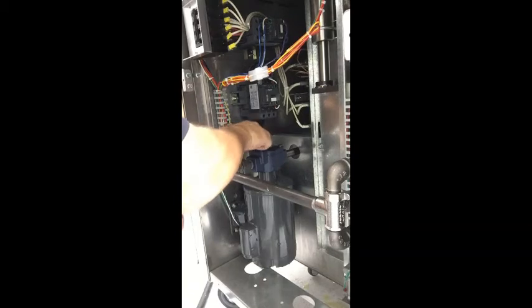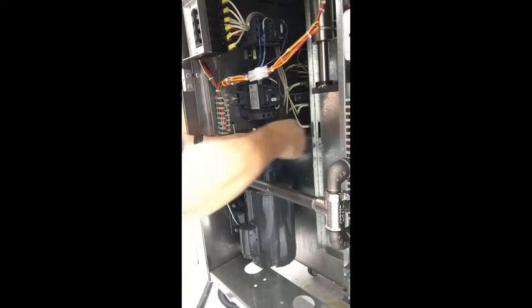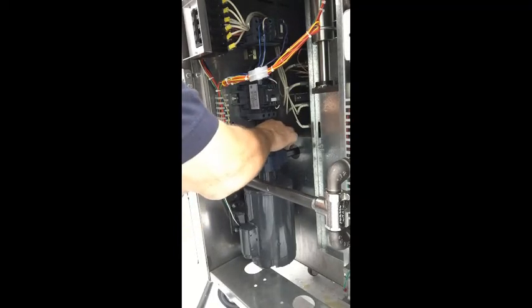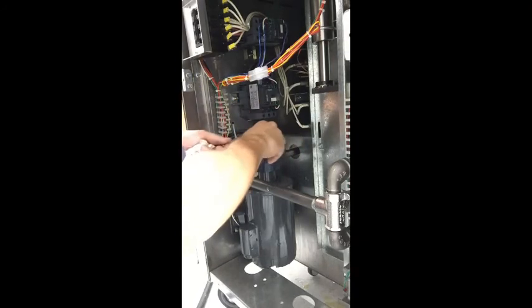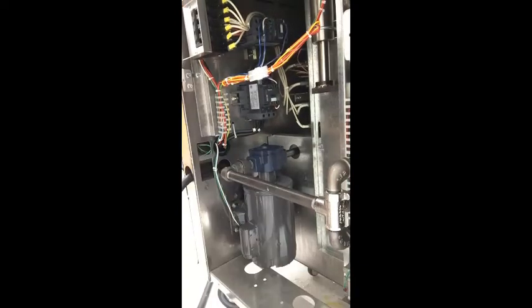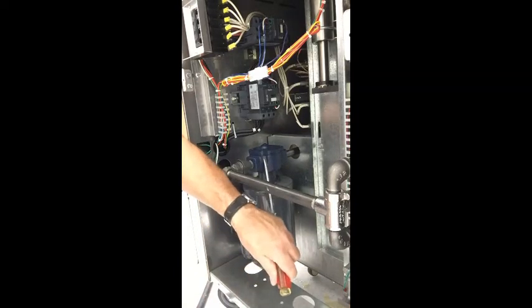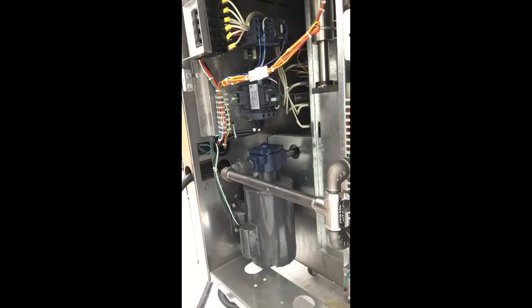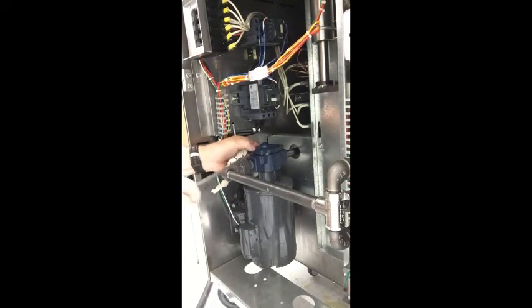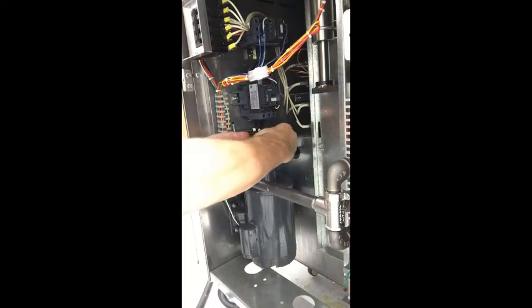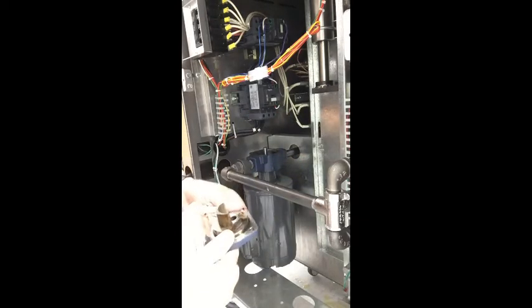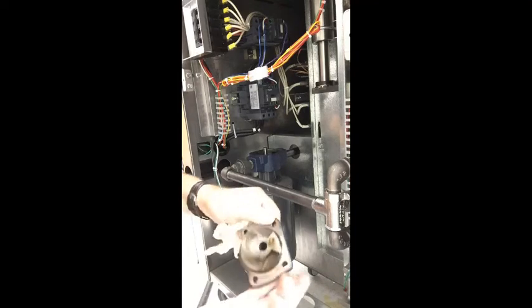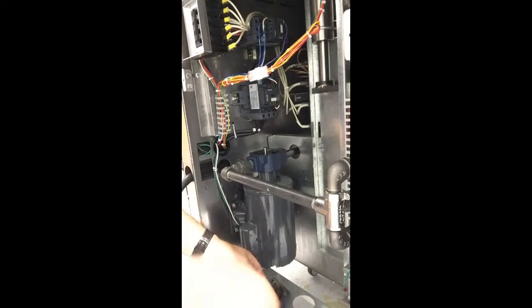Now this is a brand new pump. It's just that the unit has been sitting up for a little while. It's probably a little cleaner than what you'll see in the field many times. Okay, once all the bolts are out, you'll have to tap this cover up a little bit. You see it come up? Once that cover comes up off of there, it may take a little extra prying. Now you can see, here's the cover, and you can see where there's been a little bit of sludge and stuff that has gotten caught up in there from where it's been used.